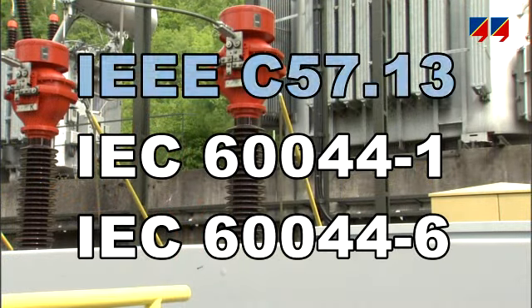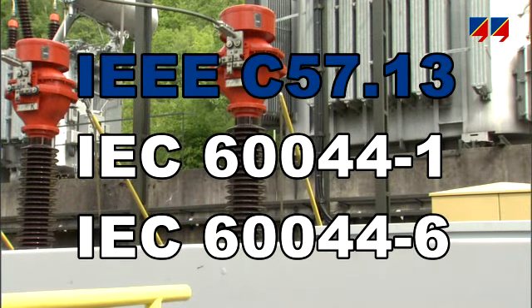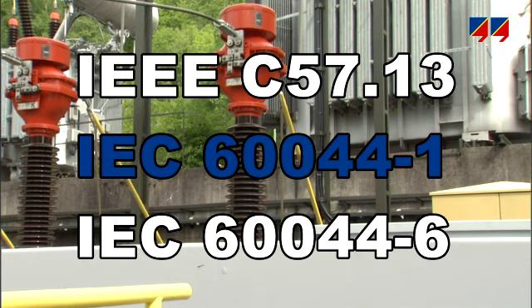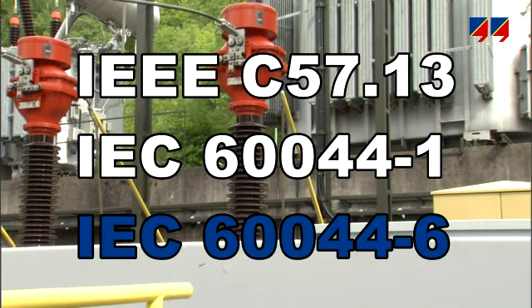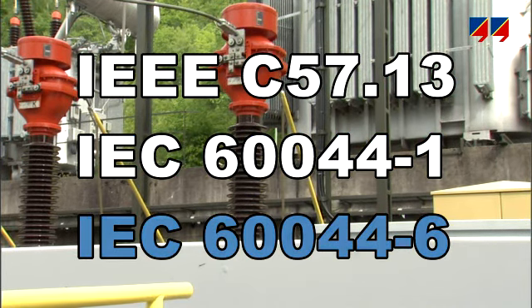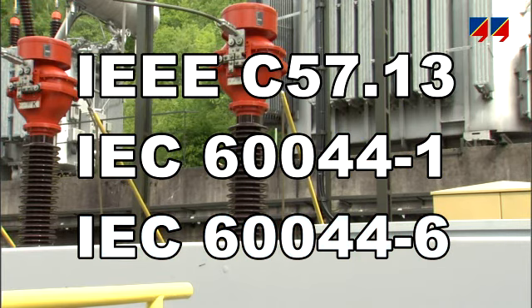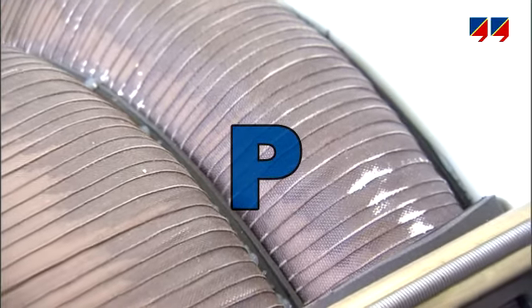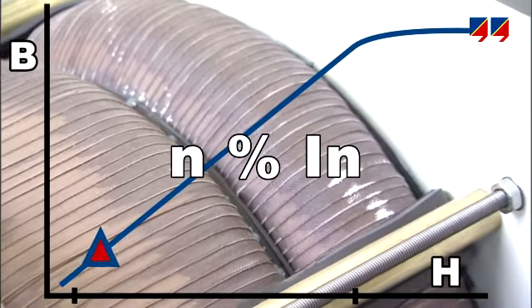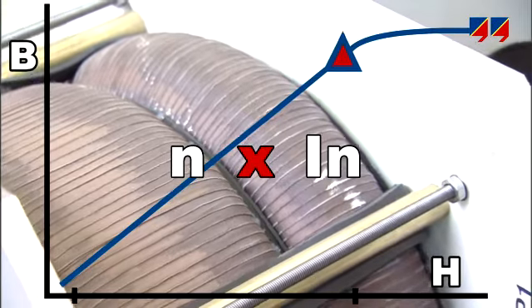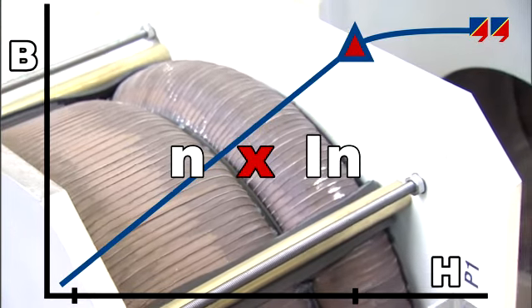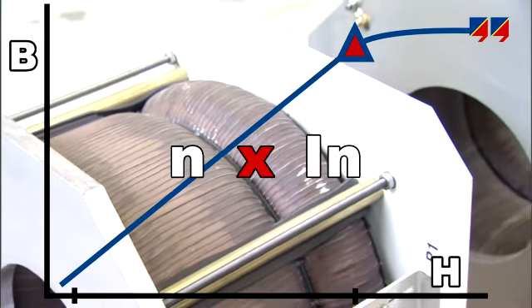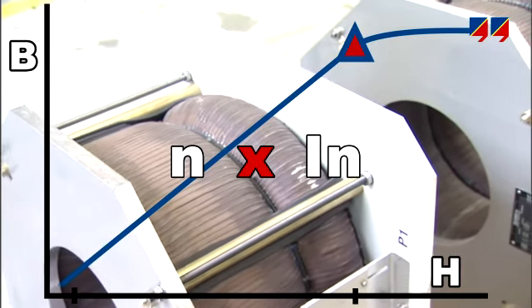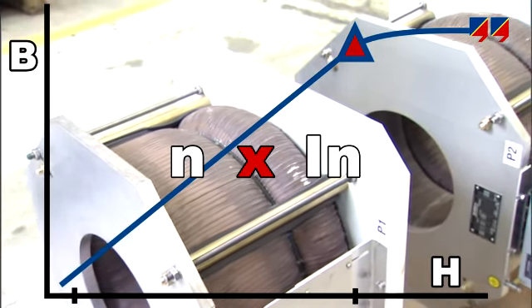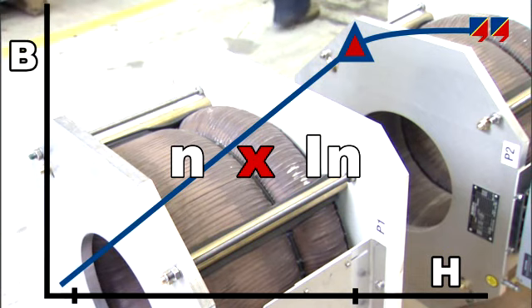International standards such as IEEE C57.13 and IEC 60044-1 and -6 describe class characteristics of protection and metering CTs. Protection CTs have to transform currents from a few percent of nominal current up to many times its value during fault conditions. The secondary current produced by the CT must be proportional to the current flowing in the power system over the whole range, within a defined accuracy.